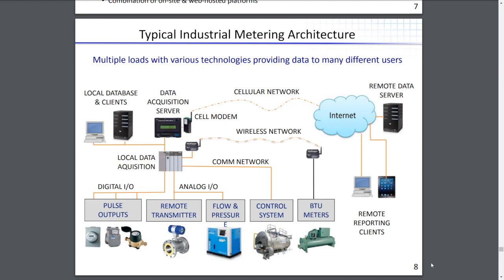Okay, so in a typical architecture, let's just start from the bottom up. Across the bottom are all the typical loads that are usually monitored. So utility meters, transmitters, pieces of equipment. And the one thing with those is each device has a different way of communicating. Right now, utility meters are pulses. Like I said, I can't wait for those to be smart meters and be able to communicate with them directly. But for each device you're talking to, there's going to be a different way to communicate with it.